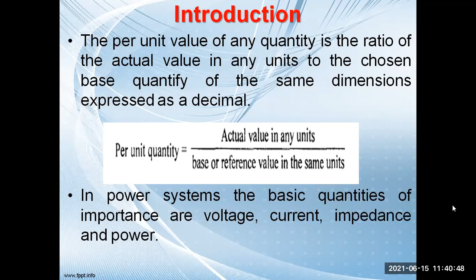For all per unit calculations, a base kVA or MVA and a base kV are to be chosen. Unless you choose the base power and base voltage, you cannot calculate current or impedance, because we know the relations: current is power divided by voltage, and impedance is voltage divided by current.